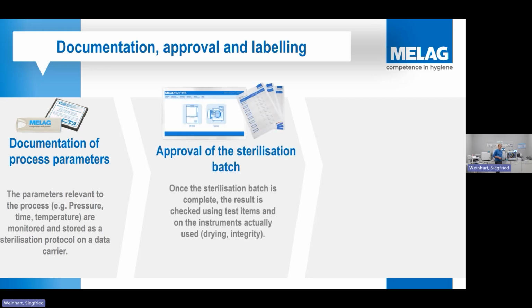Second element you've got is approval of the sterilisation batch. So that is where we're again looking at 2 ways. We may well be utilising a manual system in the form of a logbook. And in that logbook we are noting those tests that we've done. And we are noting the little stick as well, the little Helix test strip, or even the class 6 test strip for our non-vacuum cycles as well.